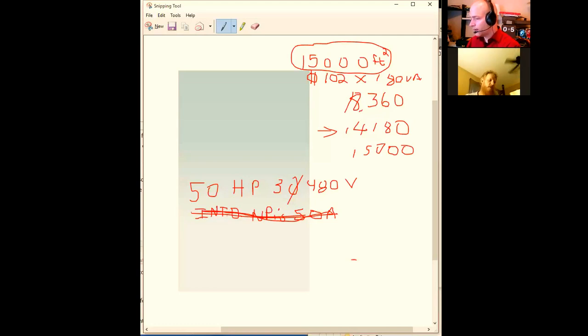Okay. All right, so that's that one. There was a generator they were telling you about in a test question. There's a generator that was providing emergency power for this building, and I might have mentioned this in class, but they were telling me that it was out of sight of the point where the conductors serve or pass underneath that building. And they're asking, what do you have to have located on that building where those conductors go inside? You have to have a directory that points out where the disconnect that's located at the generator is.